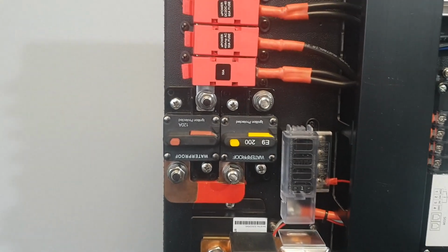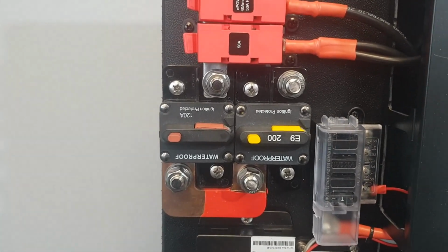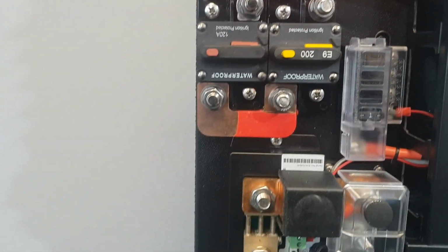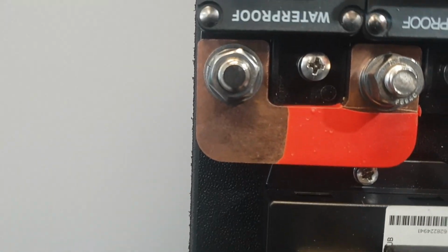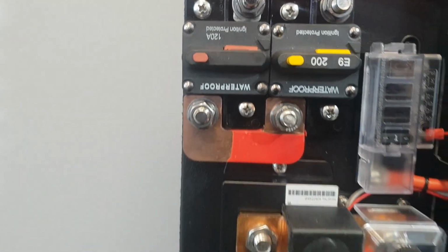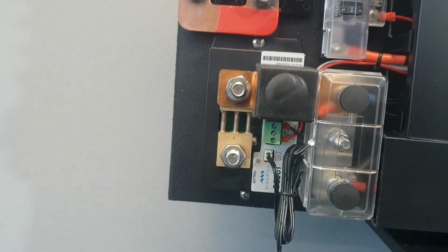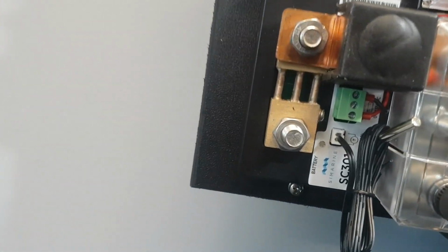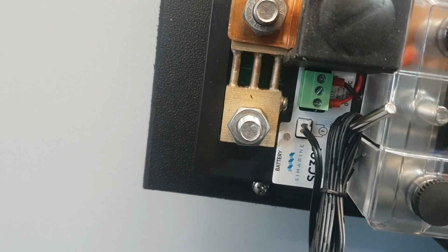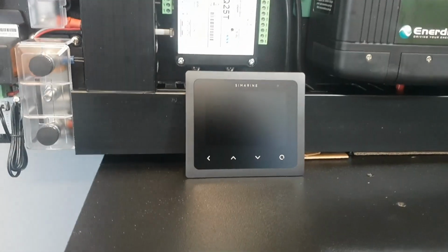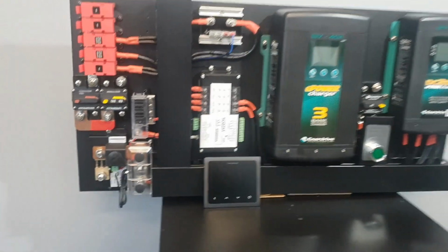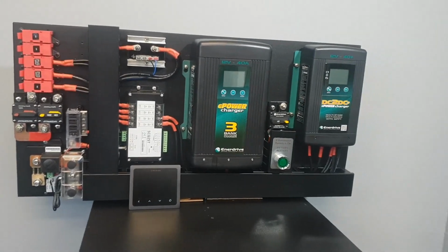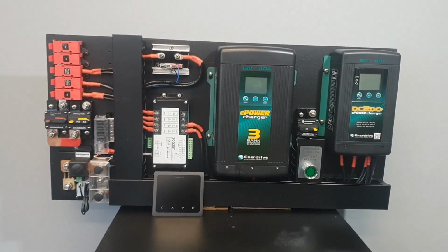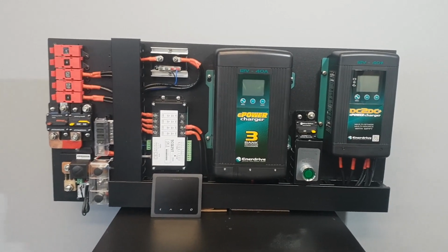As we stated before, you can connect your inverter to the 200 amp breaker. Your main battery positive feed goes on our bolt here at the bottom of the 120 amp breaker, and our main negative feed from our battery connects at the bottom there on that shunt. Run your data cable, mount your display, and then you have it, a premium system suitable for any lead acid or internal BMS lithium battery.